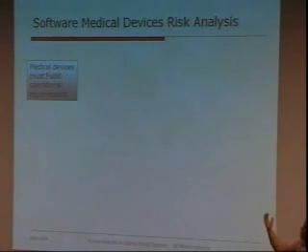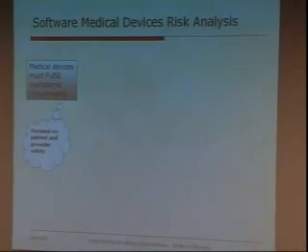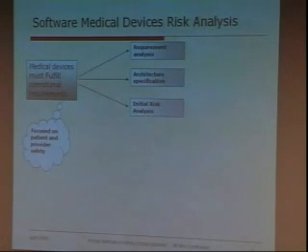So there are several key concepts regarding the risk analysis of software medical devices. Among those key concepts, in general, medical devices must fulfill operational requirements with a focus on patient and provider safety. There are several initial engineering tasks that should be done to get the operational requirements. These are requirement analysis, architecture specification, and initial risk analysis.